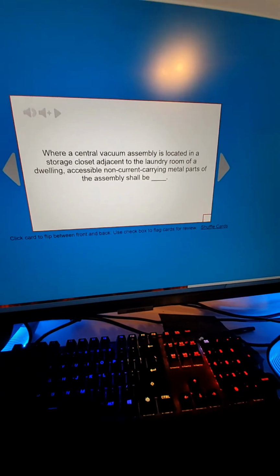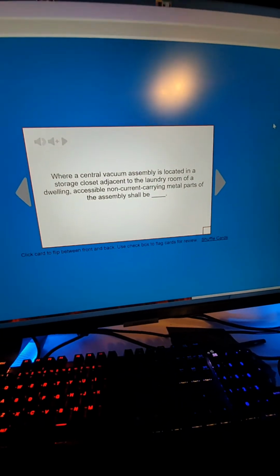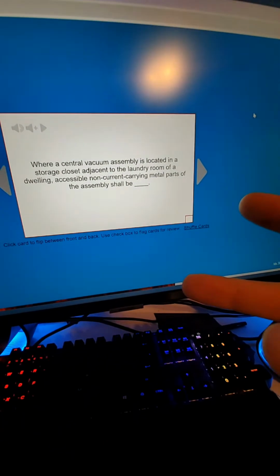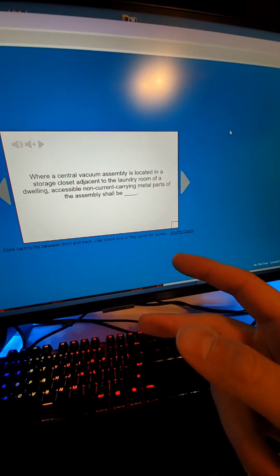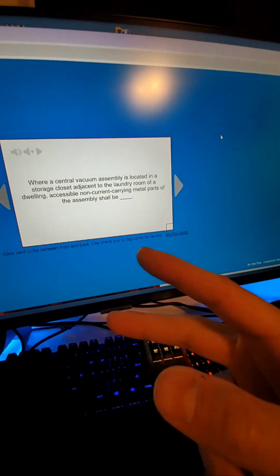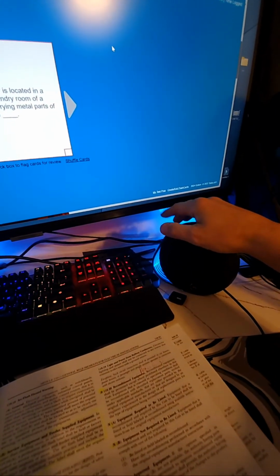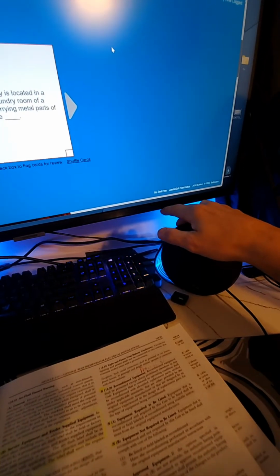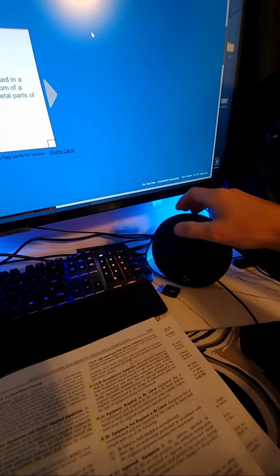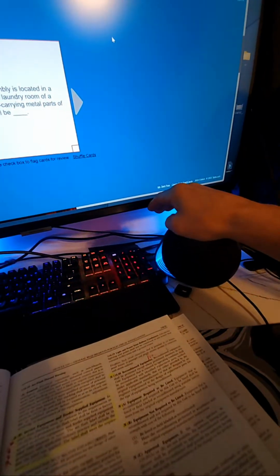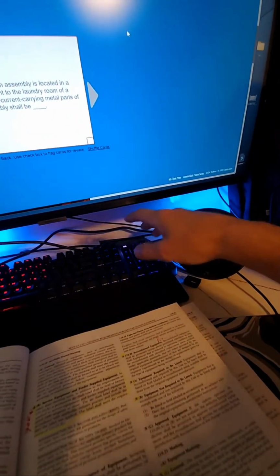Non-current carrying metal parts is the basics of bonding. It's the basics of grounding. The word's not going to be grounded. The word's going to be bonded, because you're going to attach something that doesn't have a value to give it a value, and that would be called bonding. If this speaker, if I want to make this speaker the same value as this computer screen, we need to attach it together in a reliable way. It's called bonding. If this speaker is plugged into the wall, it's grounded. If this is plugged into the wall, it's also grounded because it goes back to the source and it's got a value. But if we want to make them the same, you want to bond it.